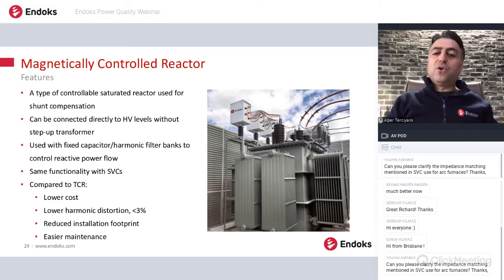And also it can be connected directly to medium voltage or high voltage. You see, because this control winding is on the same core with the main winding. So, for example, this photo is from a 36 kV system, but you can connect these MCR up to a couple of 100 kilovolts as well. There is no issue about that, and it has a lower cost, of course, lower harmonic distortion, easier maintenance.